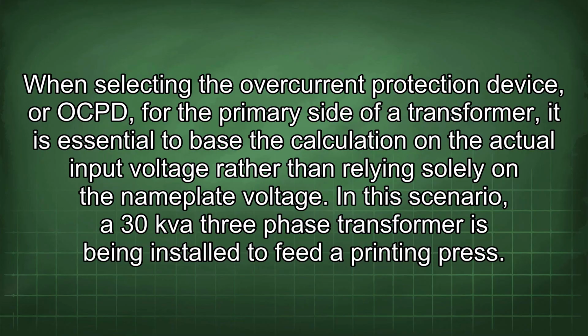When selecting the overcurrent protection device, OCPD, for the primary side of a transformer. It is essential to base the calculation on the actual input voltage rather than relying solely on the nameplate voltage. In this scenario, a 30 kVA three-phase transformer is being installed to feed a printing press.